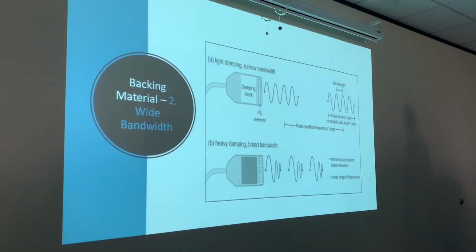Wide bandwidth is going to have a wider range of frequencies. The frequency of this sound pulse is the same throughout. All right? We good there, guys? I know I'm covering it heavy, but I want to make sure we understand the difference between wide bandwidth and narrow bandwidth, what transducers use narrow bandwidth, and what transducers provide wide bandwidth or broadband. We good on that?